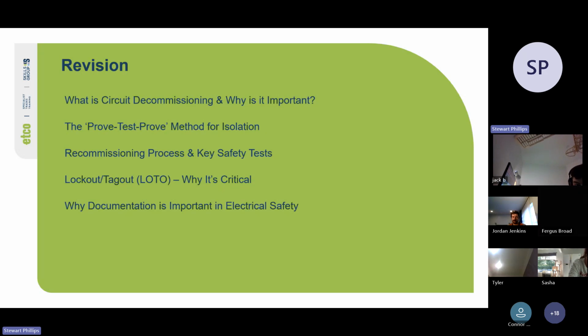Decommissioning is the safe removal or isolation of electrical equipment while ensuring that exposed energy sources remain safe. The important word there is energy sources - it's not just talking about electrical sources. It could be pneumatic, pressurized air. It could be hydraulic, pressurized liquid. It could just be normal hot water. It could be steam. It could be mechanical, a weight suspended from a high load, or tension, where something's under tension and all of a sudden it might release tension and shoot out.